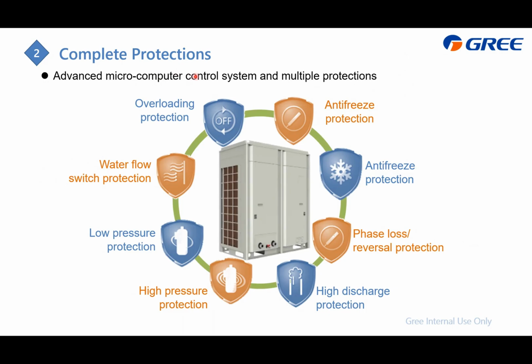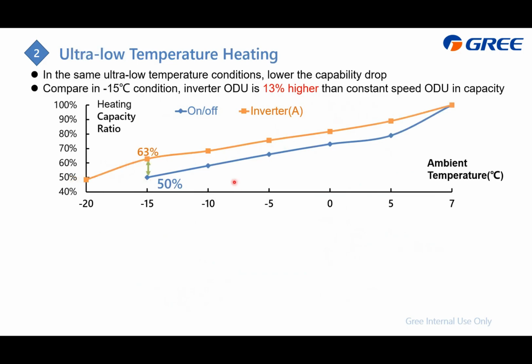Complete protection. From the design stage, we already considered all the protections, including for the compressor, which is in this slide. First, we display the heating capacity in low temperature condition, which follows this one. This orange line is the inverter A series, and the blue line is the on-off. You can find that we can raise the compressor RPM higher, especially in low temperature heating. For the on-off, the lower limit is only -15, because after that we cannot ensure it can operate. For the inverter, we can go as low as -20. Comparing at this part, we can increase the heating capacity by 17%.